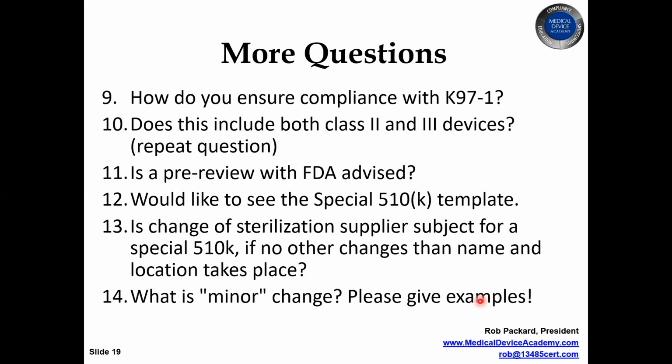Okay, how do you ensure compliance with K97-1? So earlier when I presented the guidance documents at the beginning of the presentation, I indicated that the new device modification guidance document replaced K97, so that's no longer eligible. But yes, you ensure compliance by going through that guidance document and making sure you meet the requirements of it. They have a new flowchart in there that's been updated.